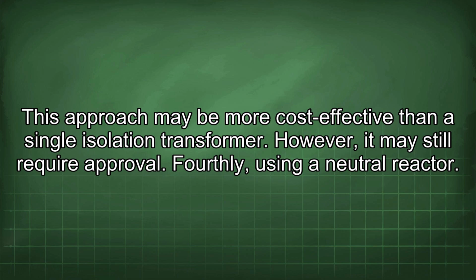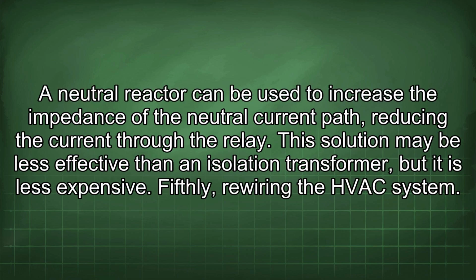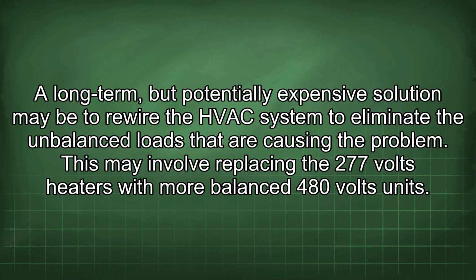Fourthly, using a neutral reactor. A neutral reactor can be used to increase the impedance of the neutral current path, reducing the current through the relay. This solution may be less effective than an isolation transformer, but it is less expensive. Fifthly, rewiring the HVAC system. A long-term, but potentially expensive solution may be to rewire the HVAC system to eliminate the unbalanced loads that are causing the problem. This may involve replacing the 277 volt heaters with more balanced 480 volt units.